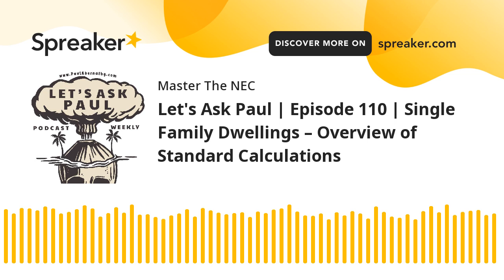If it's a concrete-encased electrode, it does the same thing. You're going to go to 250.66(B), and (C) would be a ground ring. If they don't state the type of electrode, then you're just going to go to table 250.66 in general, and it's based on the size of the service conductors. Okay? Pretty straightforward on all of that information. None of that's overly confusing at any part.